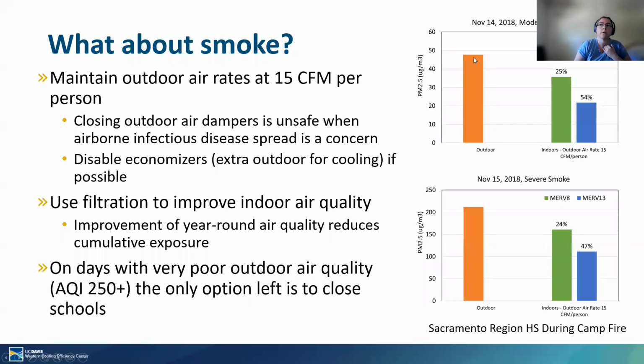You can see here our outdoor air particulate matter and our indoor air particulate matter. And you can see that the air quality inside the MERV 13 classroom was much better. No portable air cleaners in this case either. And this was like a moderate smoke day. You can see outside was like 50 micrograms per meter cubed. And this was a more severe smoke day, outdoors 200 micrograms per meter cubed. And so anyway, you can see that we can really reduce the concentration indoors by like half with just using that MERV 13 filter and still ventilating.